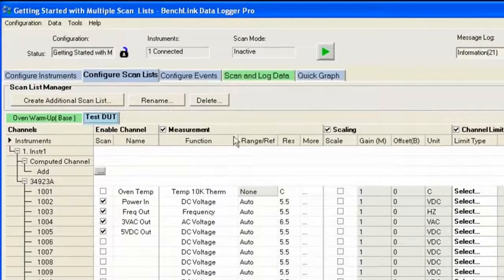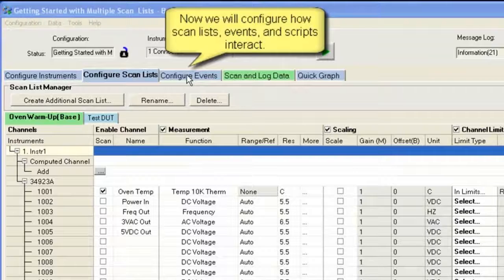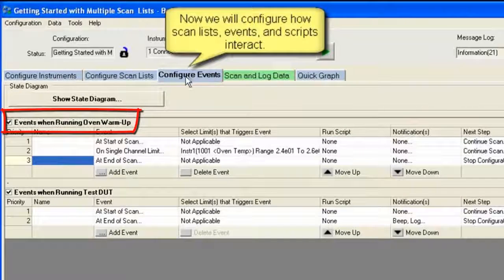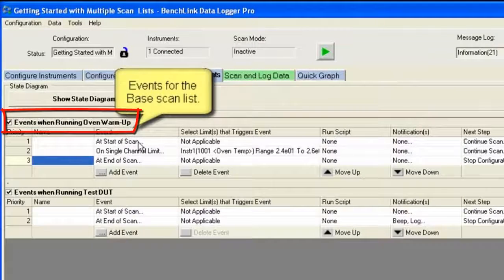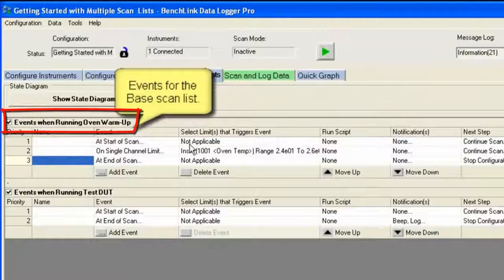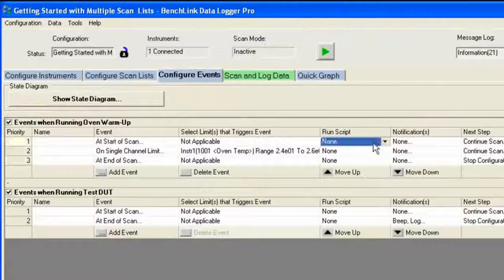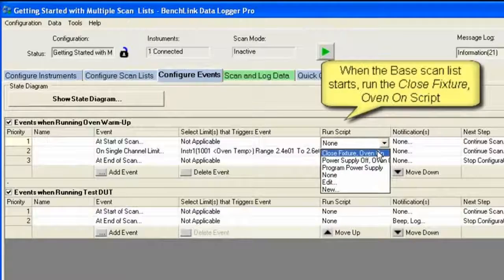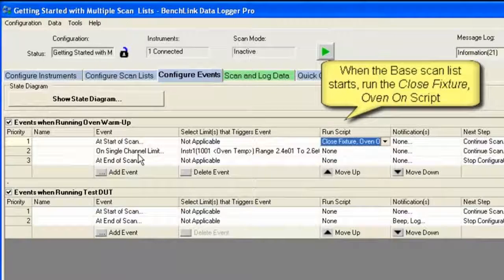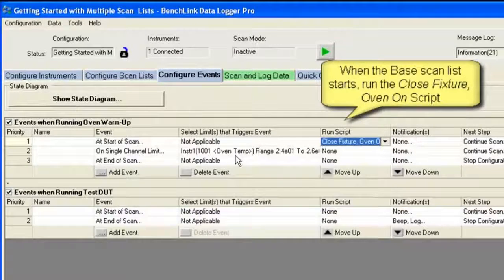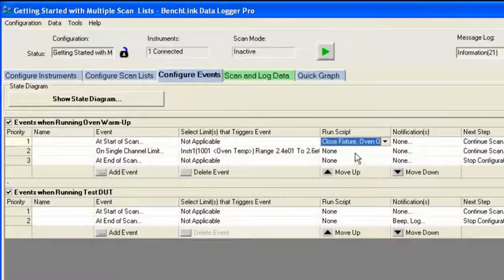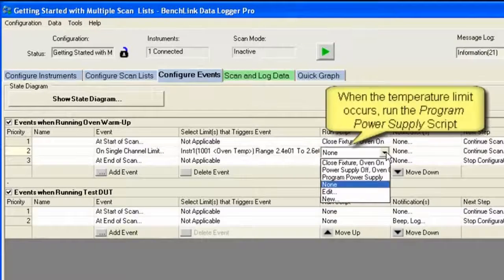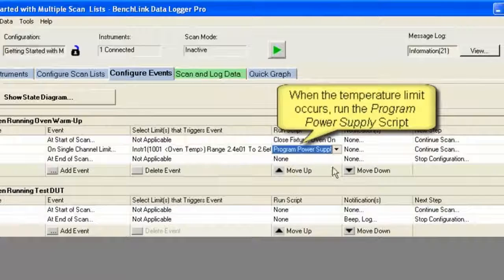And we're going to configure events and show you how the scan list, the events, and the scripts all interact. So the events that you want running during the warm-up: first off, we're going to start the scan, and we're going to close the fixture and turn the oven on.